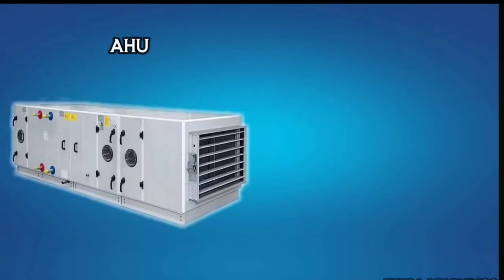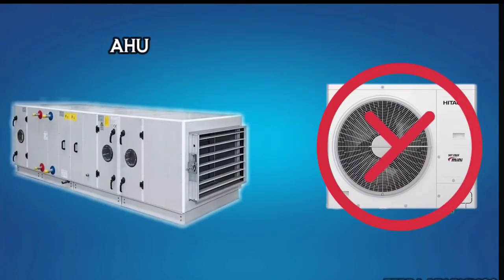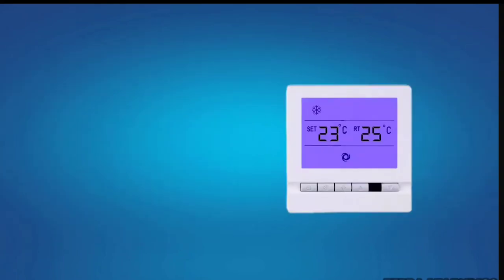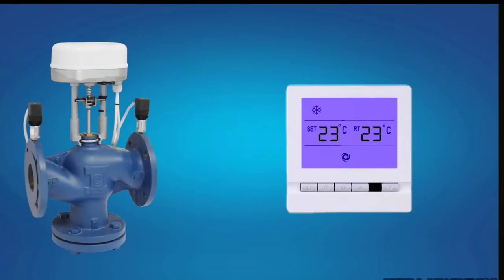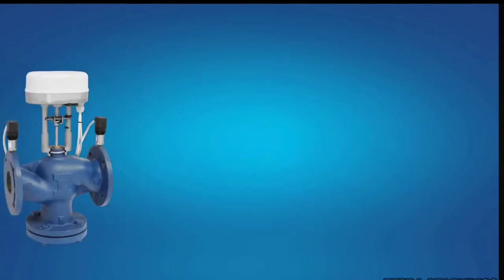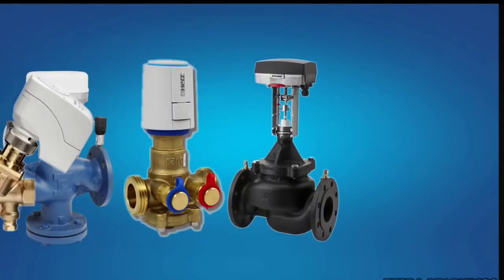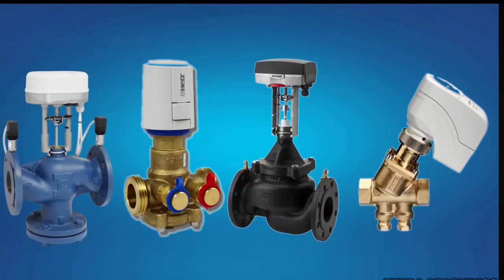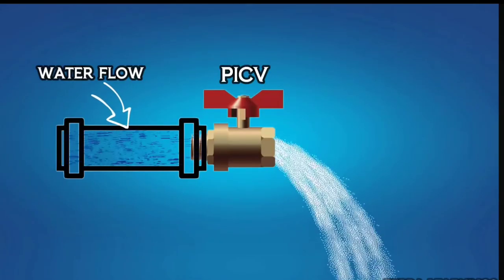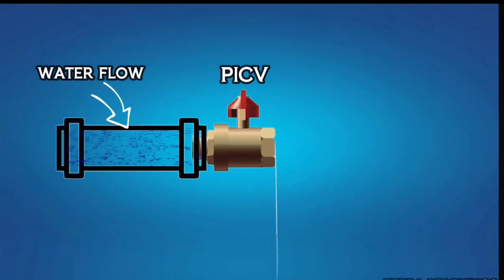But in AHU, there is no outdoor unit, it works like an indoor unit. So, if the temperature of the room reaches the set point, the PICV will work like an outdoor unit. Let's know how PICV works. We can see PICV in many designs, but they all work on the same concept. PICV works like a normal valve. It's stopping and opening the flow of water in the chilled water pipeline.